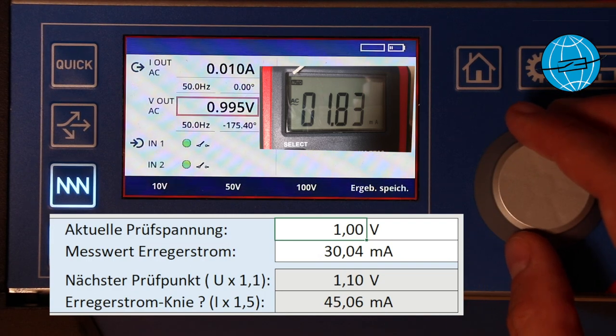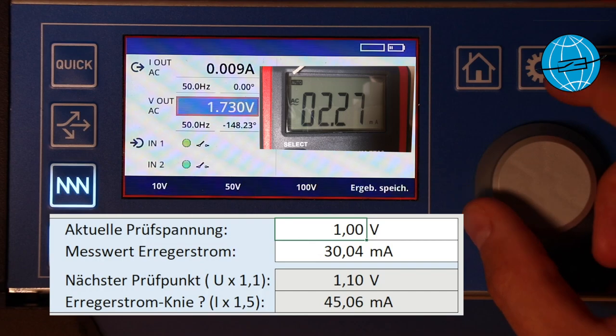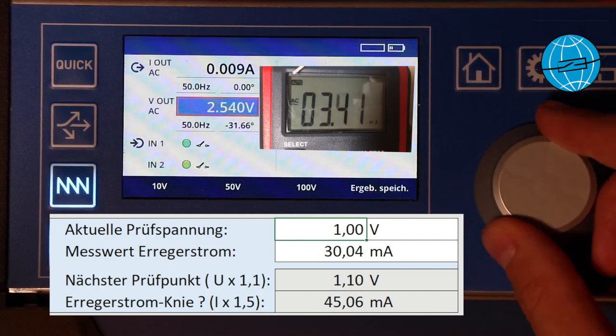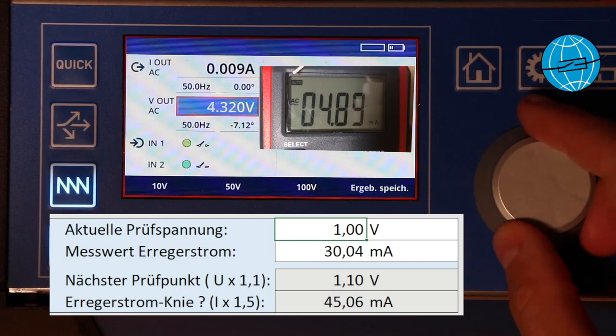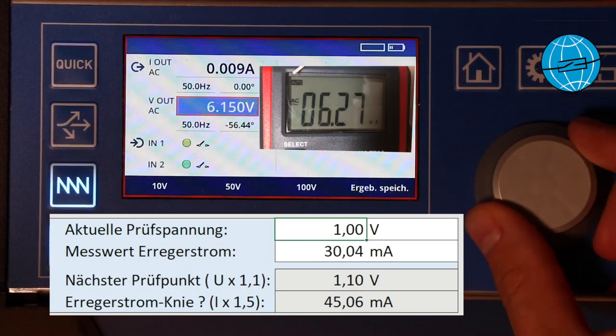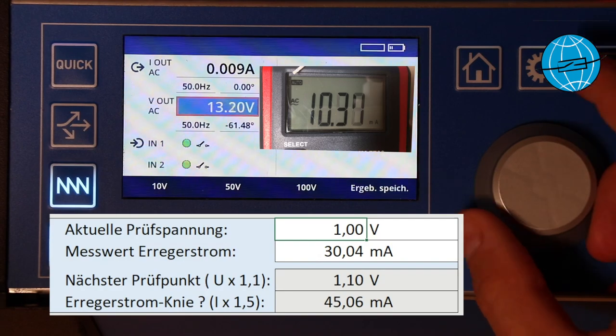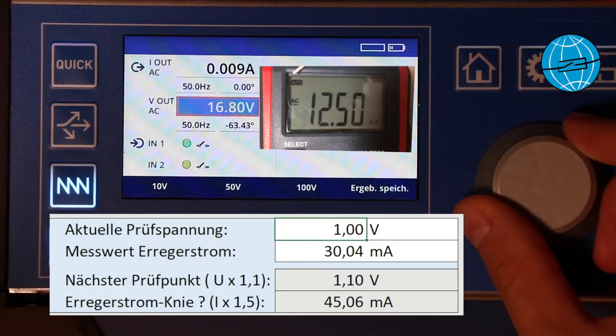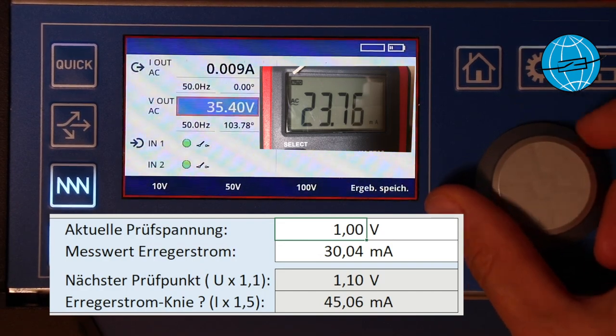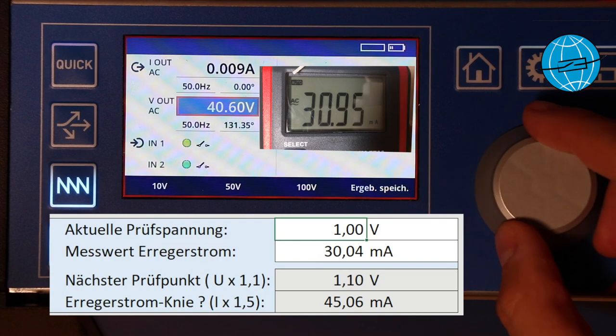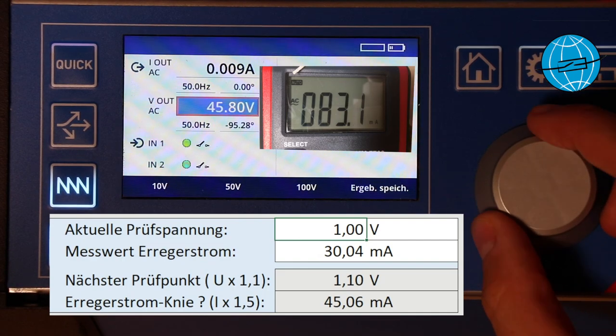We are starting our test now by the voltage of one volt and increase the voltage in a slow and even way. Please don't mind about the German labels on the checkbox below. If you download our Excel tool you will find an entire English version of course. So all we have to do now is to find the value of the voltage when the current suddenly rises sharply. We keep on increasing the voltage, we are not shy, we can do this and we always have an eye on the current. We have about 20 volts and the current still moves slowly higher and we keep on increasing the voltage. 35, 36 and suddenly it happens the current starts to jump up and we find the voltage about 40 as starting point for our measurement in detail.